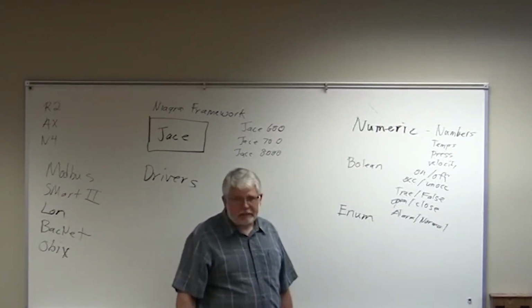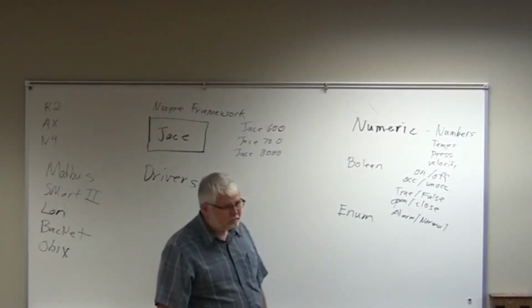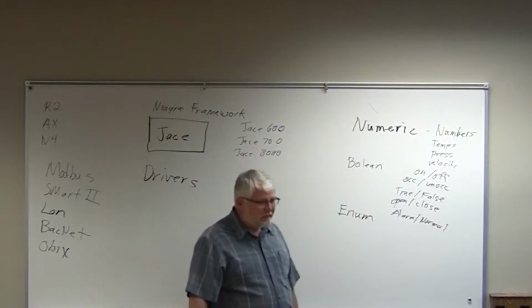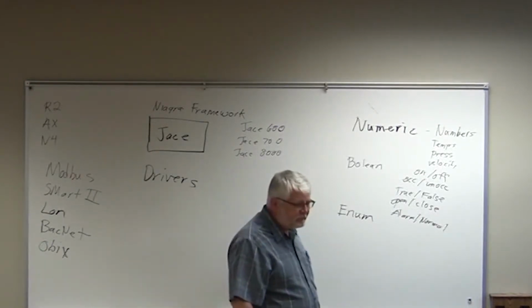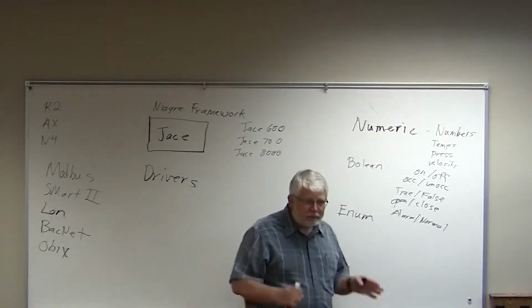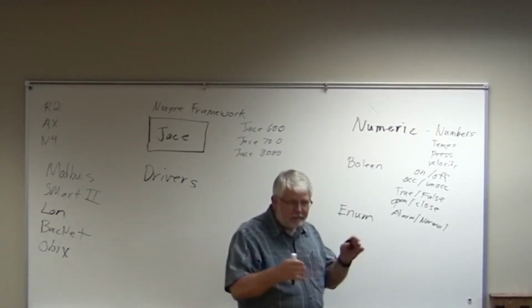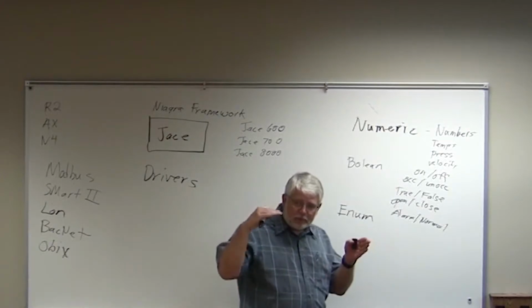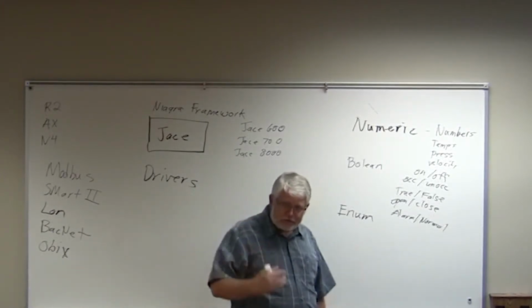What's an enum object? Anything that has more than 2 states. Like occupied, unoccupied you got there, but if it's got a warm-up mode or cool down mode, or a variable high, medium, low. It has multiple states, so they're like integers, right?